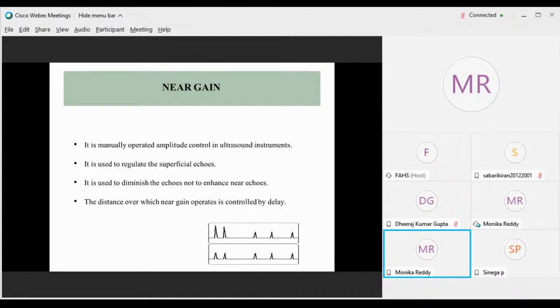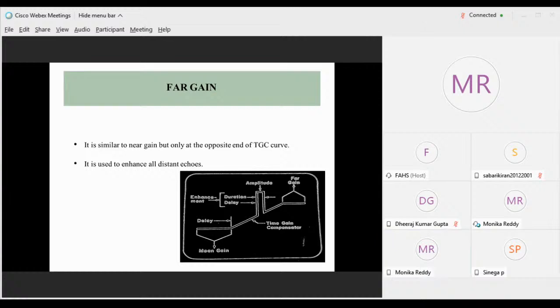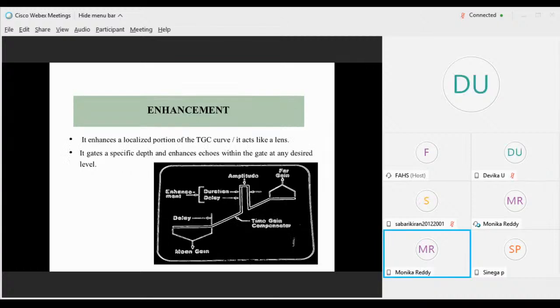The near gain is a manually operated amplitude control used to regulate the superficial echoes, to diminish them, not to enhance near echoes. If the near echoes are enhanced, the far echoes will not be enhanced properly and will not be visible. So the near gain control diminishes the enhancement of the near echoes. The far gain is the opposite of the near gain control; it enhances the distant echoes. And the enhancement control adjusts echoes within the gate at any desired level.